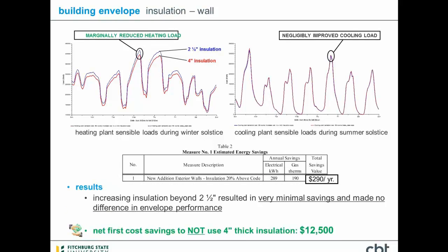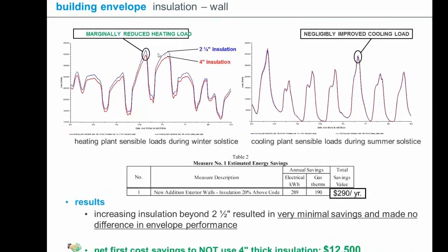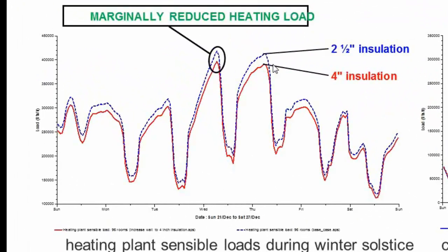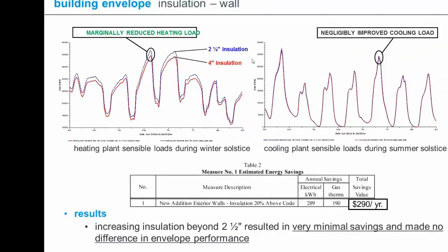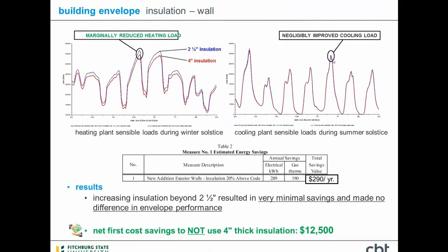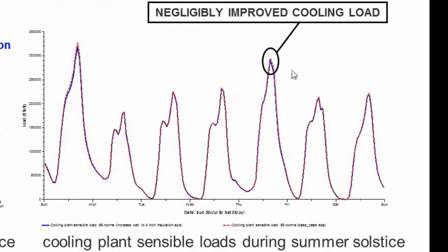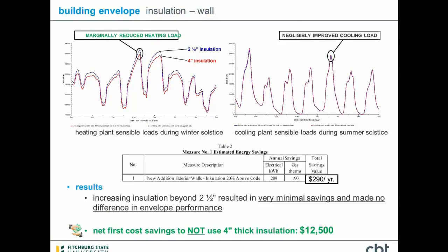And what we actually found out was that while there was a fairly noticeable reduction on the peak week here that we're looking at between the peak heating loads between the 2.5 inch simulation and the 4-inch case, on the cooling side it was almost not noticeable.